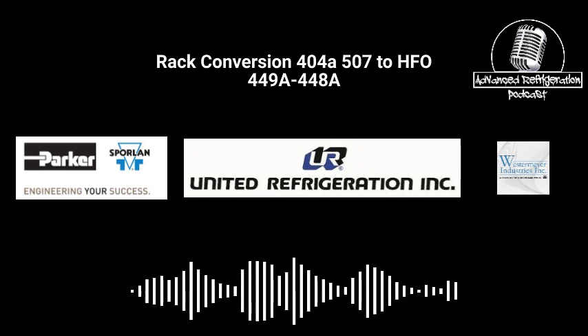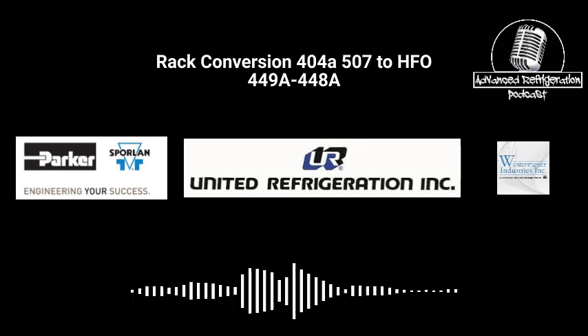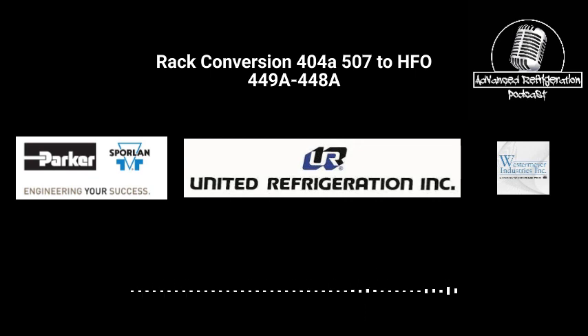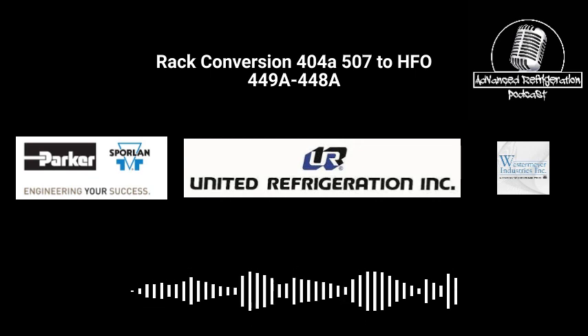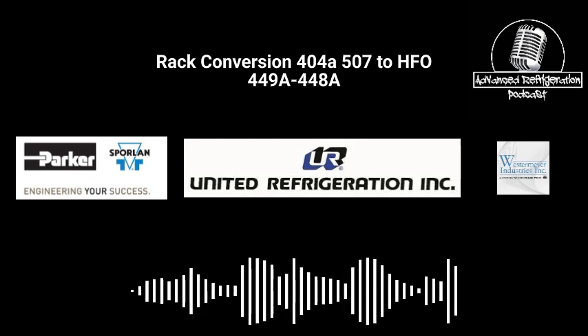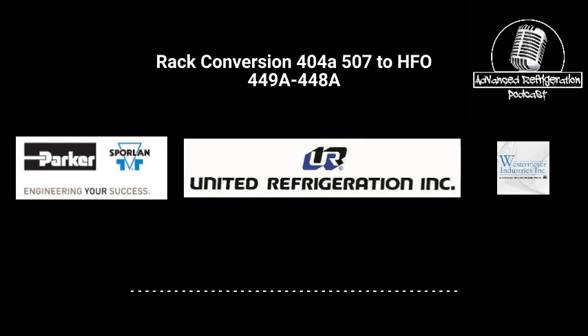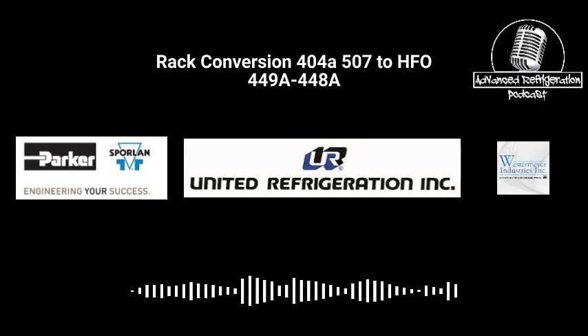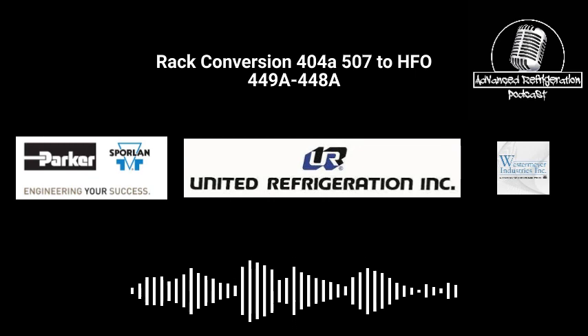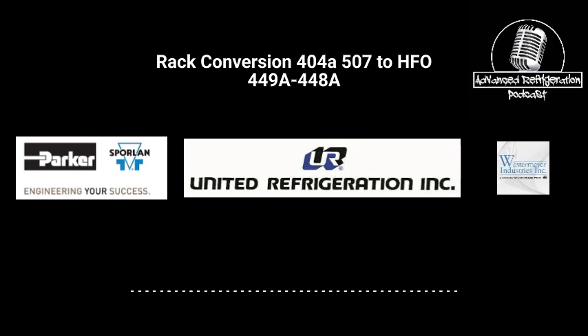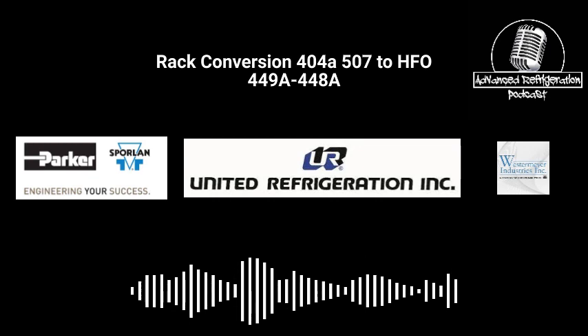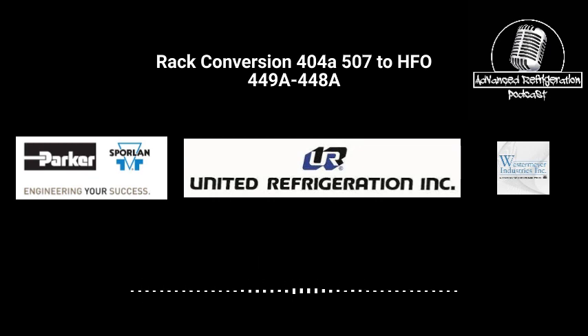Now, this is where it gets tricky, because if you do the power heads before, you have to open the valves up. You have to open the valves up because you're going to have 448 suction pressure in there, or I'm sorry, 507 or 404 suction pressure, and there's a closing force, and you're going to have an opening force that's way less on that R22 bulb. So you're going to have to open the valves up, maintain the case temperatures and superheat. So generally, it's like a turn and a half, 2 turns.